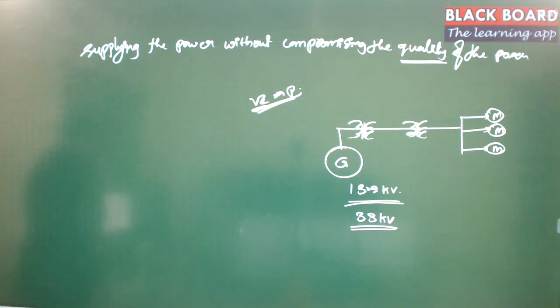So 13.2 kV is the exact voltage we usually generate, but the current can be increased, so even though V is less, the power can be compensated by generating it with a higher current. Higher current can be achieved by keeping more conductors, and if the area of cross section is higher, the resistance is less, and if resistance is less, the I square R loss is less.